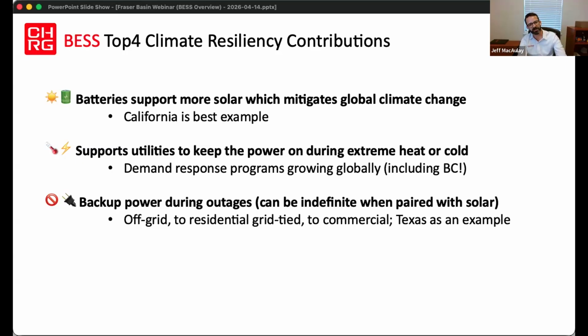This historically made sense off-grid. Now we're seeing it more in residential and grid-tied applications, and commercial is another area it applies. In commercial, a lot of people who needed backup already have diesel generators, but there can be disruptions to machines even with a couple seconds of startup, automatic transfer switch cutover. So many commercial applications would prefer an online standby device ready, even just for the first hour or two. We're seeing commercial backup go up as an example too.